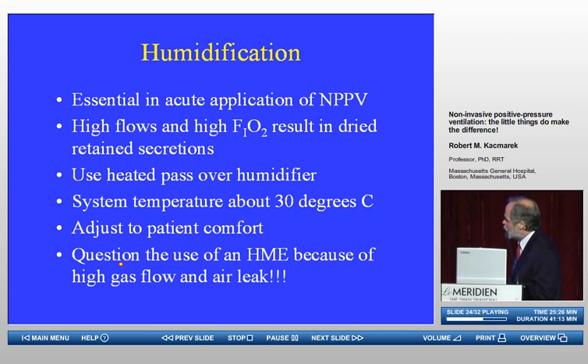I put here a question mark about using heat and moisture exchangers. I say this because, remember, for a heat and moisture exchanger to function properly, you have to exhale through it and then re-inhale through that. With non-invasive ventilation, the volume moving back and forth can be quite different on each breath, as well as between inspiration and expiration, as a result of leaks.